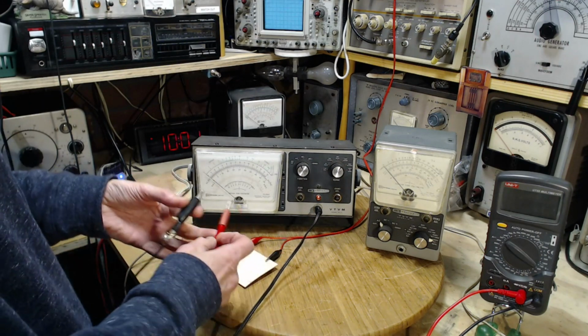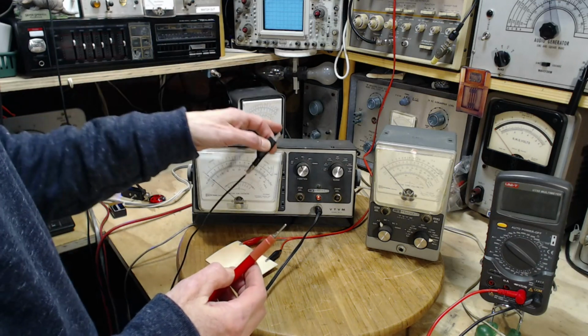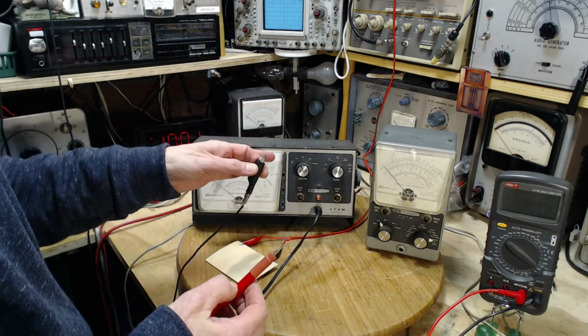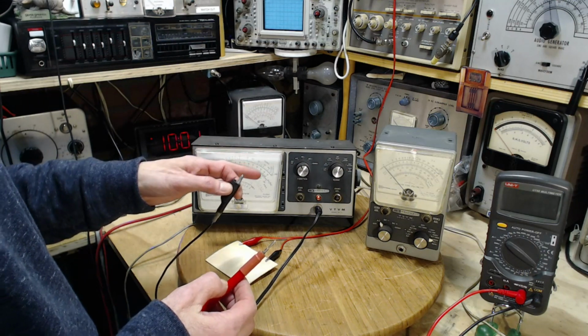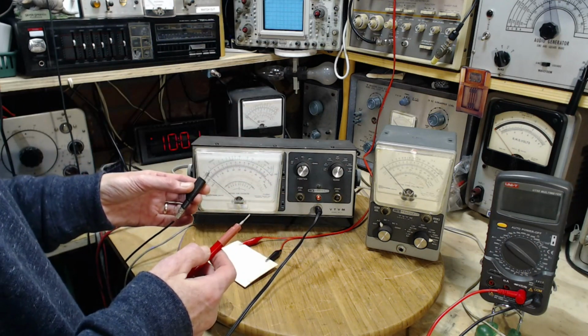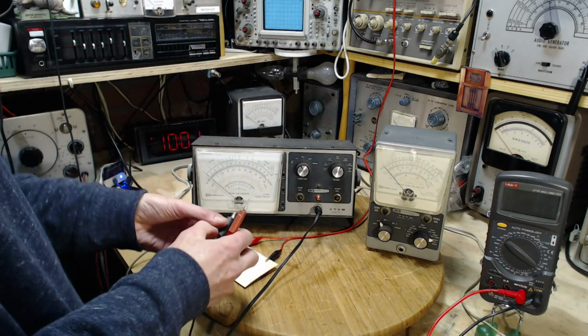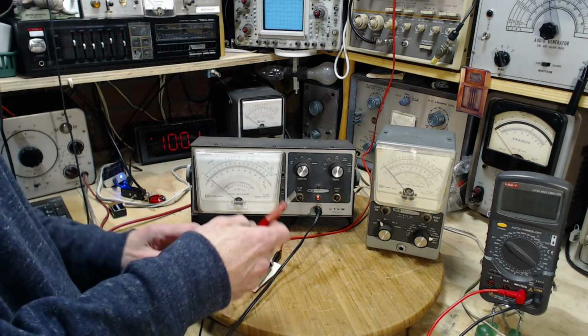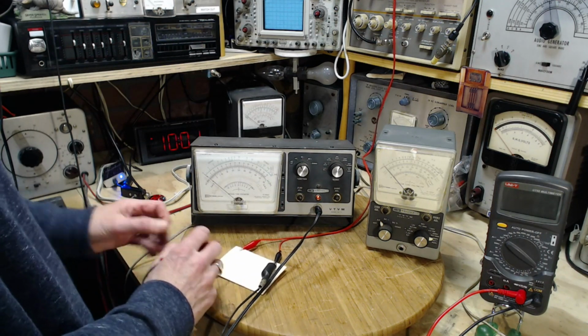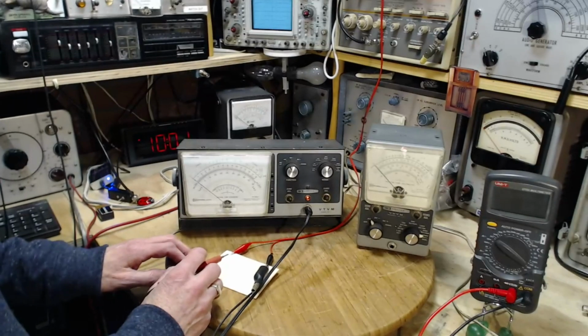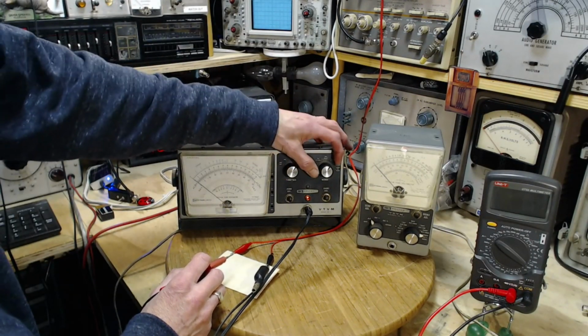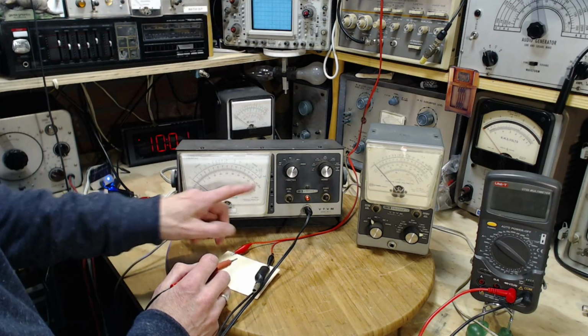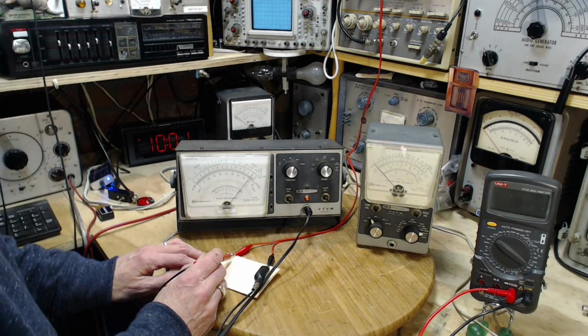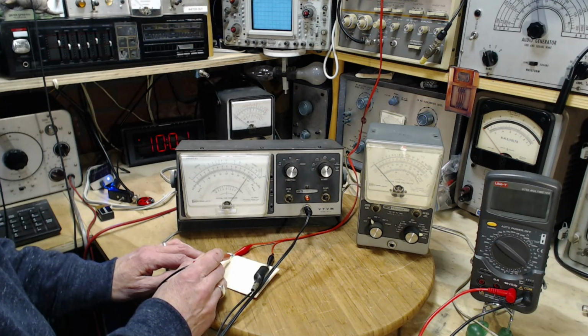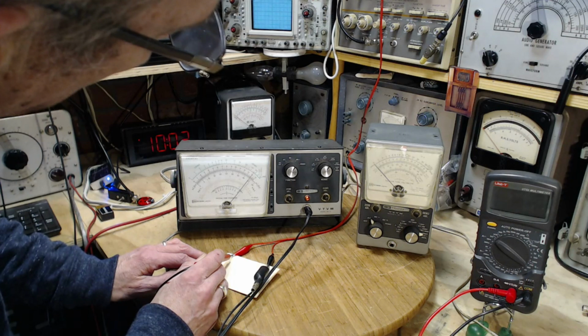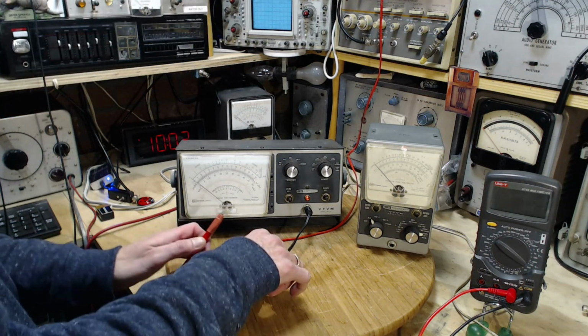Don't think there's an issue with the ground connection. There's a two-prong plug, no feed through this device back to the power neutral, unless something funny's been done to it. So we shouldn't really be able to get a short circuit of that type. Put this on here. These are all famous last words you're hearing me say. Okay, so we're going to put this on DC because we're smart enough to do that. 150 volt scale. This should come right up to there and stop. So I see 140 there. Dead on 140.